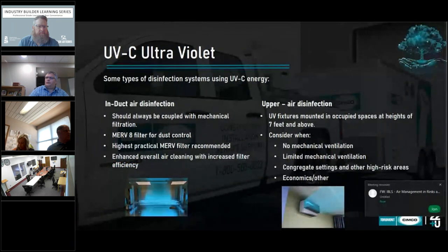There's a lot of different UVC out there, a lot of different types of disinfection systems. I think some of the facilities and types of facilities I see in Saskatchewan that would be very effective would be in-duct. So for those that have systems a bit newer and more complex, you could essentially look at putting the UVC right in your air ducts. Again, couple it with mechanical filtration - you'd want a minimum MERV 8 filter in play for dust control. However, if you can go to a higher efficiency, it's certainly a recommendation, and it works very well.